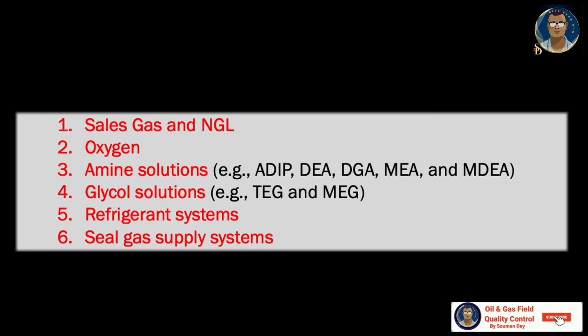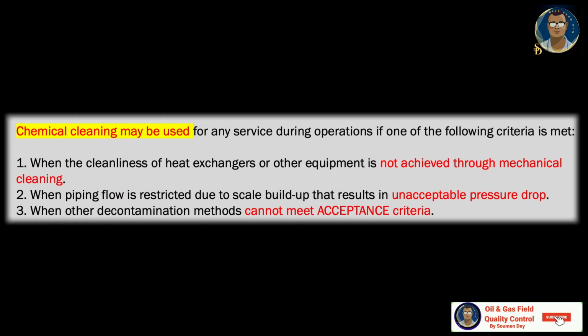Chemical cleaning may also be used for any services during operations if one of the following criteria is met. Number 1, when the cleanliness of heat exchangers and other equipment is not achieved through mechanical cleaning. When piping flow is restricted due to scale buildup that results in unacceptable pressure drop, or when other decontamination methods cannot meet the acceptance criteria.